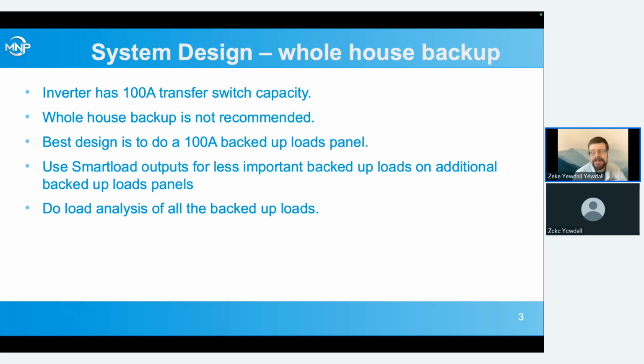Recommended that you do a separate backed up panel and use the extra smart load outputs for less important backed up loads on separate sub panels. And then you can segregate your loads and pick which ones are more important, which ones turn off sooner.